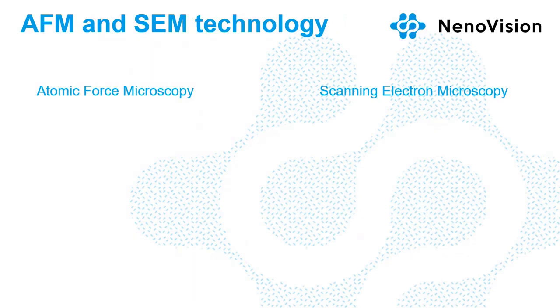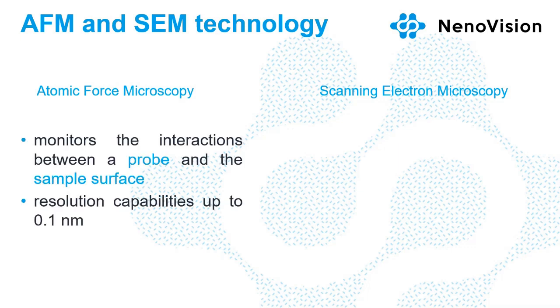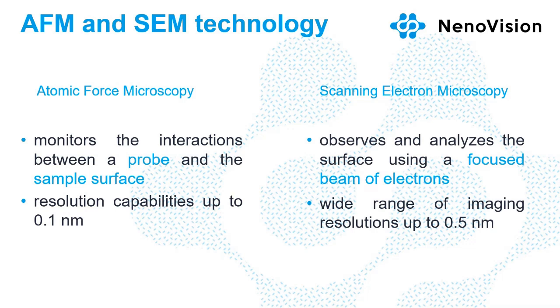So atomic force microscopes and the scanning electron microscopes are two of the most used and in fact complementary techniques for the sample analysis in the nanoscale. Nevertheless, since the principles with which we observe using this AFM technology or SEM technology are quite different. AFM monitors the interactions between a probe and the sample surface, and it has very high resolution in that direction. On the other hand, scanning electron microscopy observes and analyzes the surface using a focused beam of electrons. So it has very good resolution in X and Y.